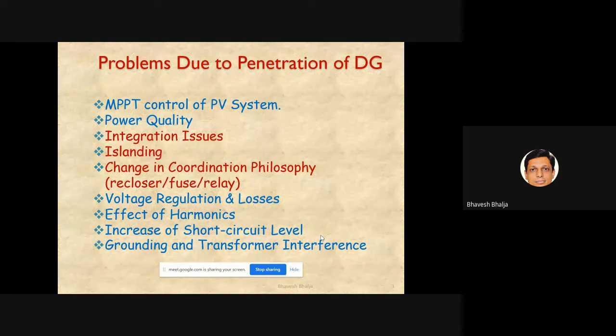Even the current in the neutral conductor also increases, because when I design the neutral conductor in a three-phase four-wire system at 415 volt, I consider the cross-sectional area of the neutral conductor to be half of the phase conductors. But because of harmonics and deterioration of power quality, the current in the neutral conductor exceeds. So now the practice is that the cross-sectional area of the neutral conductor should be the same as the phase conductor, right? So cost increases because of this. Of course there are some other impacts also, okay.